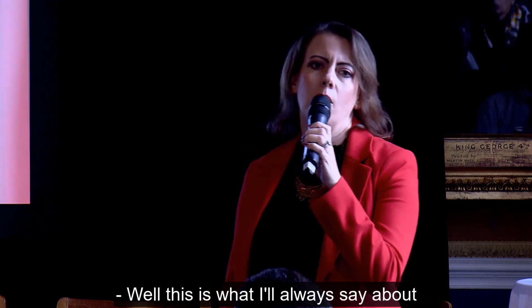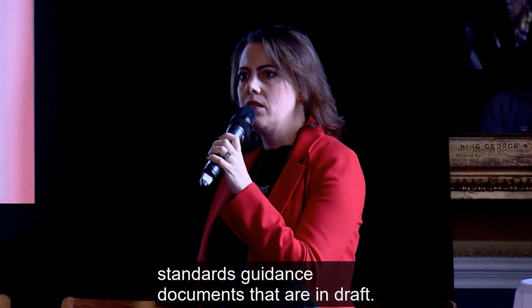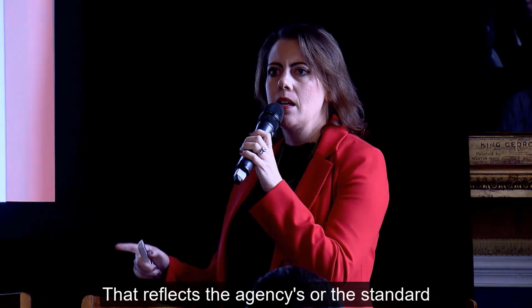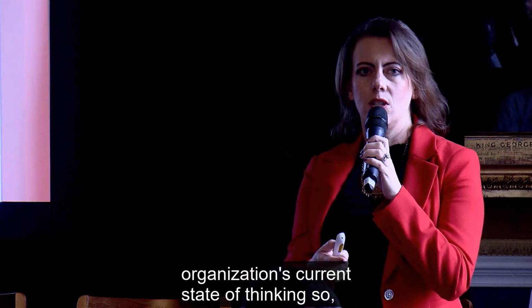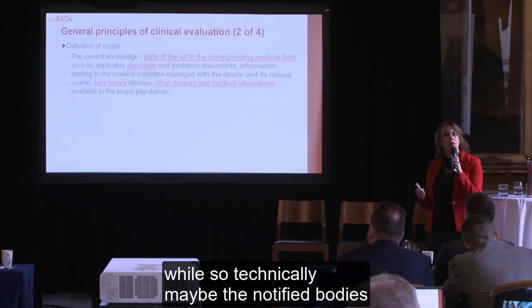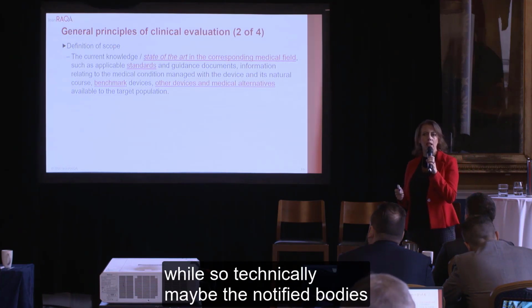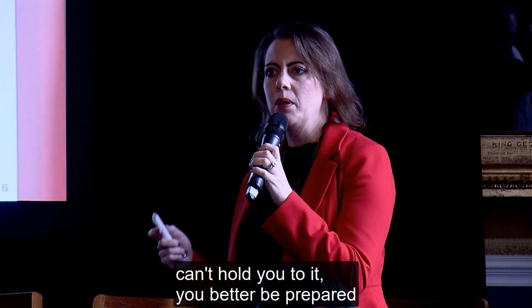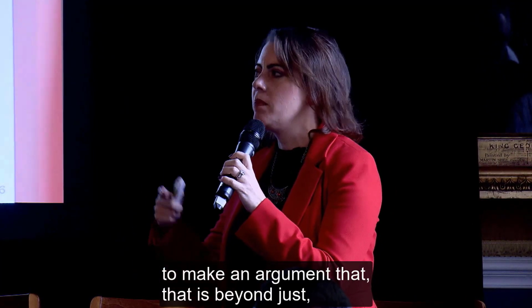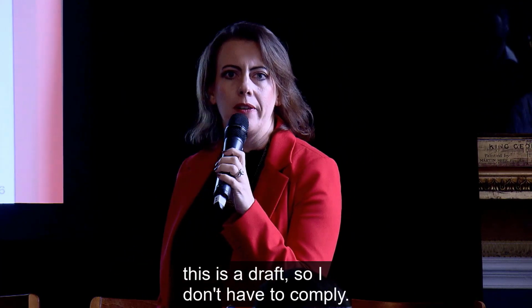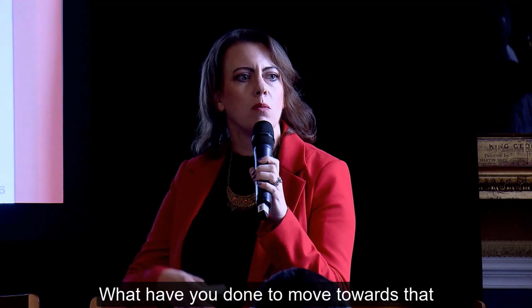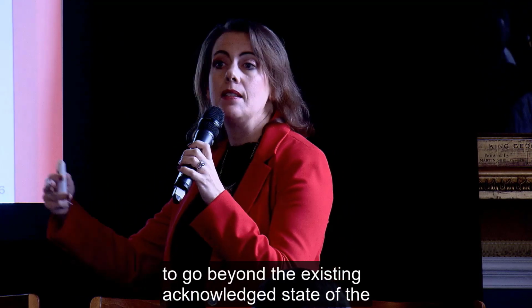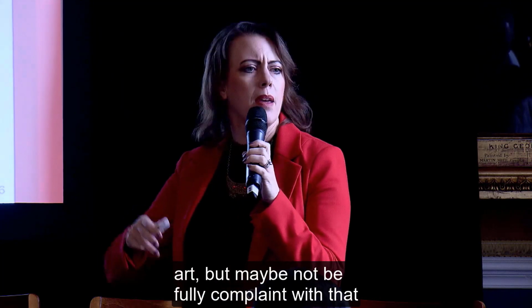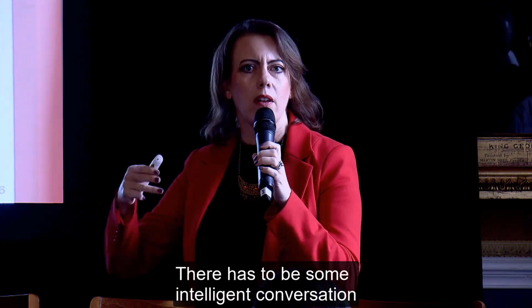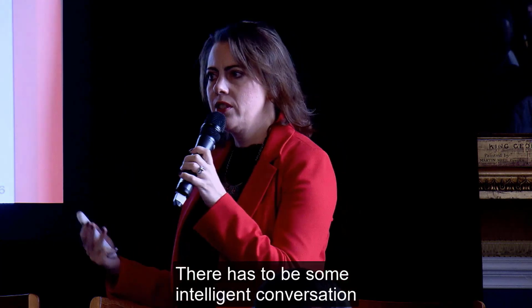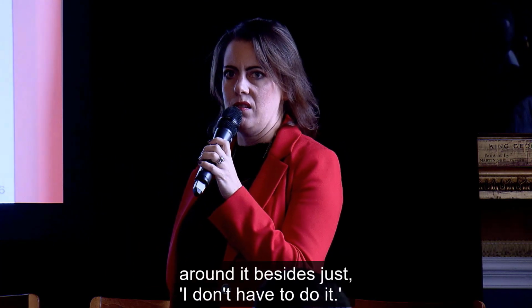This is what I always say about standards and guidance documents that are in draft. That reflects the agency's or the standard organization's current state of thinking. So while technically maybe the notified bodies can't hold you to it, you better be prepared to make an argument that is beyond just, this is a draft so I don't have to comply. What have you done to move towards that, to go beyond the existing acknowledged state of the art, but maybe not be fully compliant with that new standard? There has to be some intelligent conversation around it besides just, I don't have to do it.